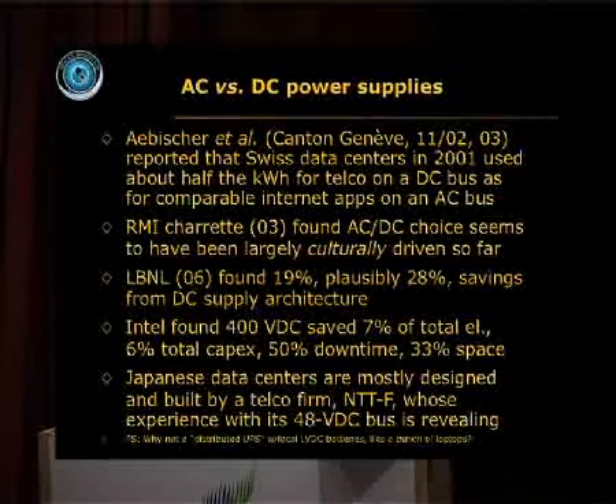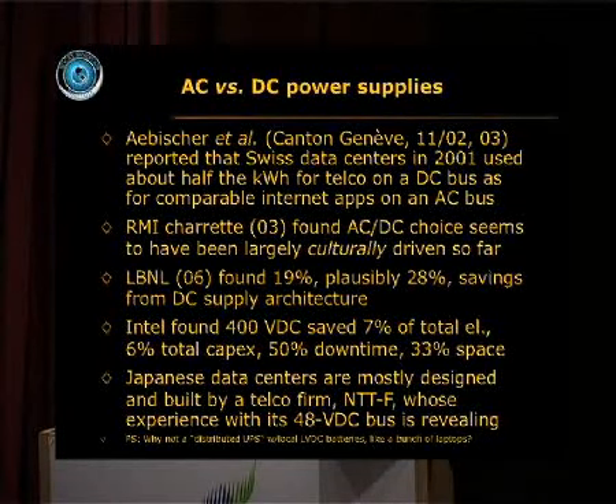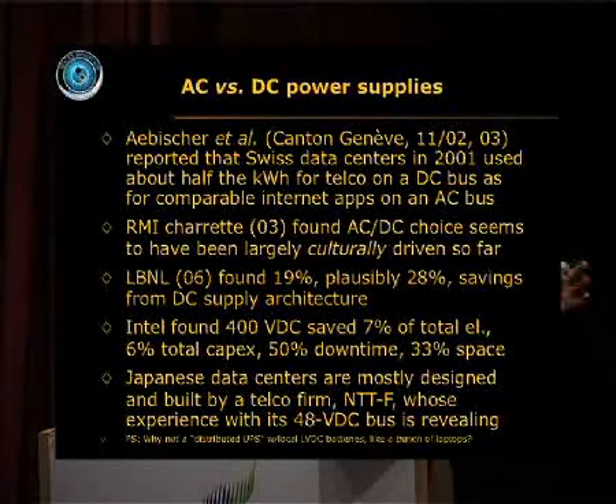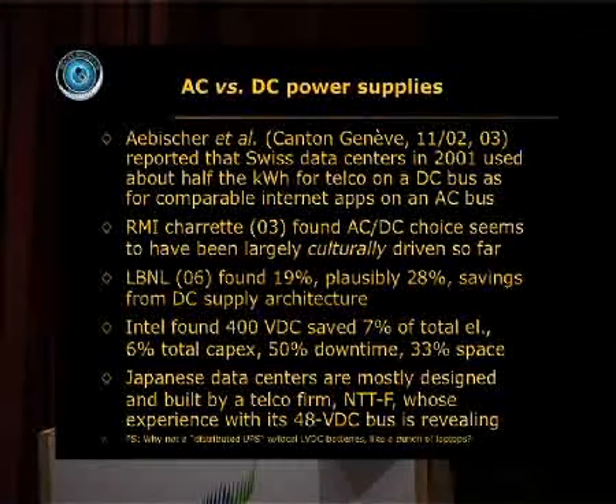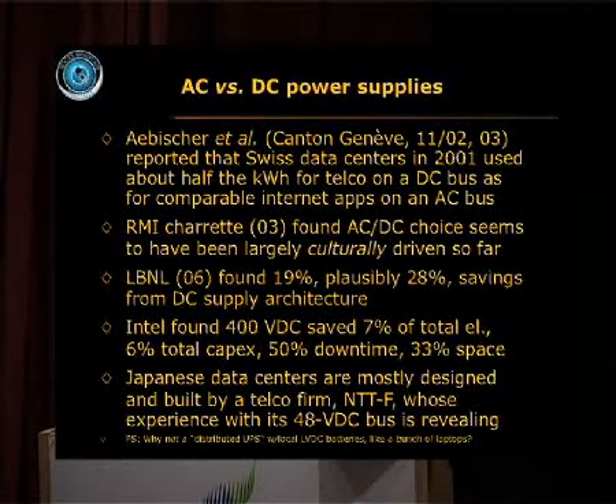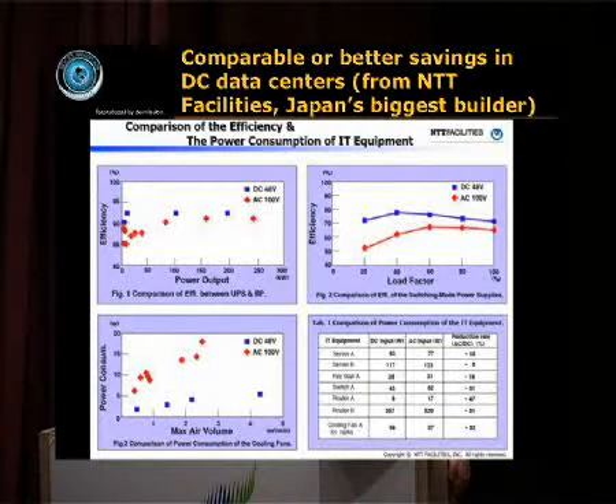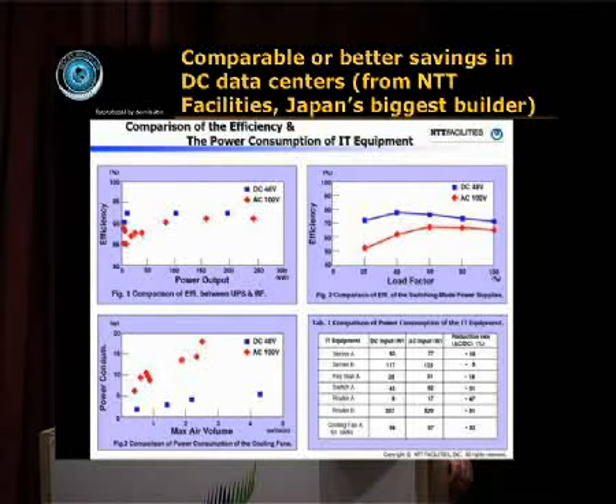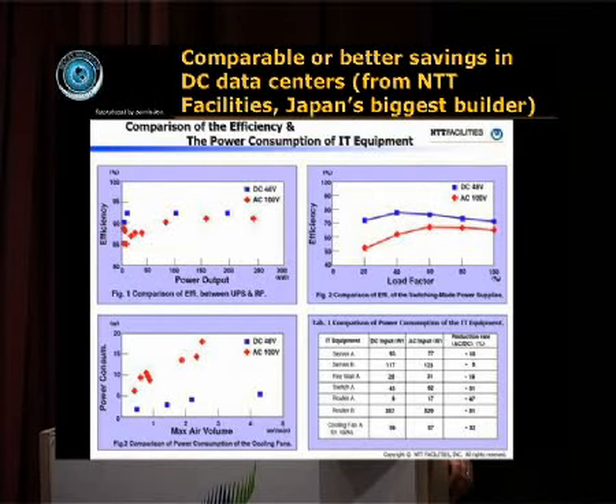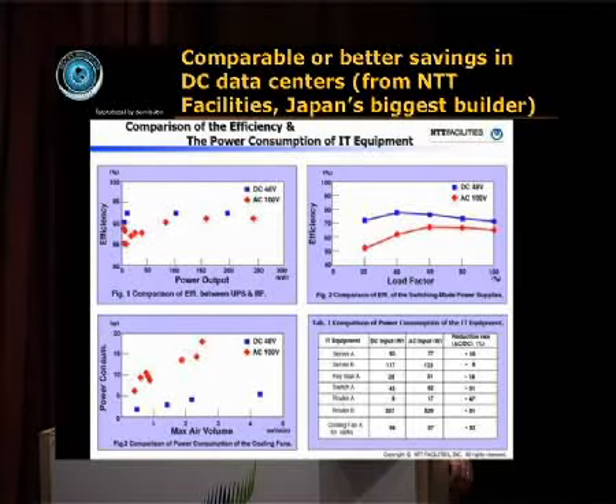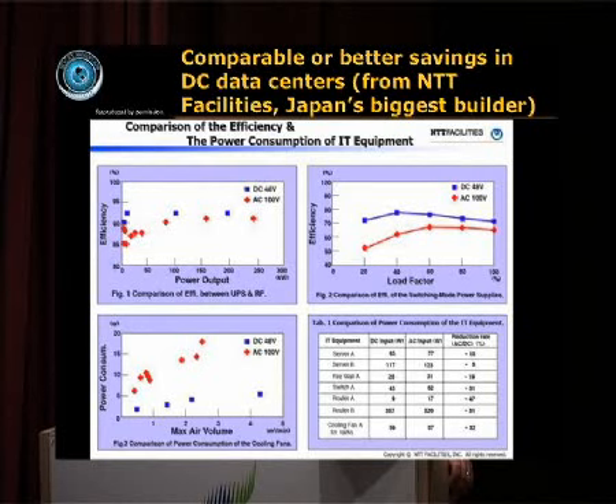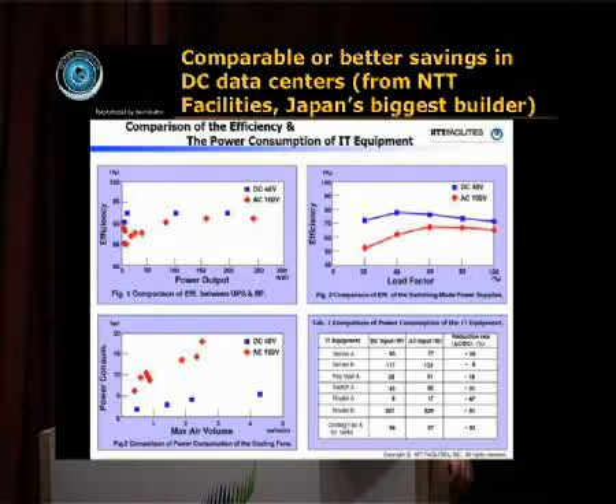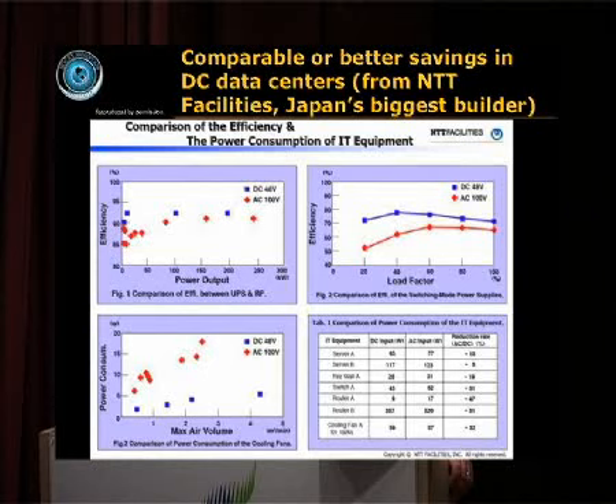Of course, one other architecture that comes to mind is, why not have a distributed uninterruptible power supply, have a bunch of local low-voltage DC batteries, just like you're running a bunch of laptops. Not a completely crazy idea. But here's what NTT found. Look at the DC 48 volt efficiency as a function of power output versus the AC 100 volt efficiency. Look at the system load factor. Look at the air volume, much less needed for DC than for AC. And these are the kinds of reductions they're getting by going to DC.